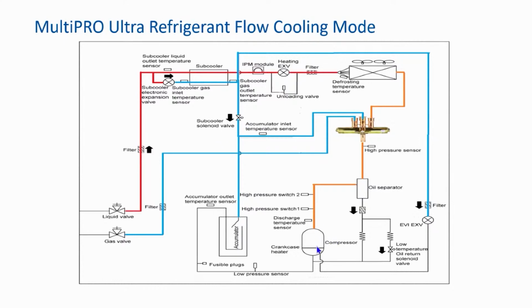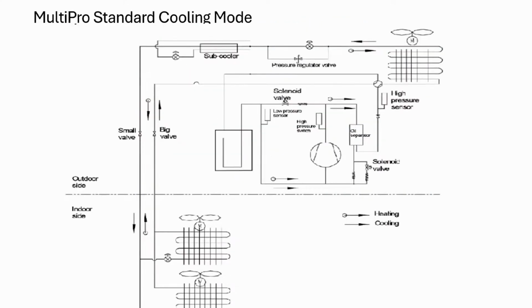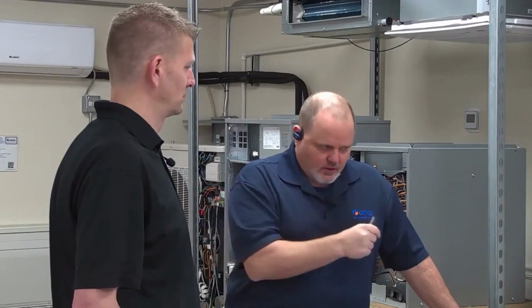In other words, the speed of the compressor, the speed of the outdoor fans, the speed of the indoor fans, what step the EEVs are at, whether you're in heating mode or cooling mode. They don't have to be wide open, right? So we'll go back to this diagram, because we need to understand this better once I get that service tool in my hand, and I'll start talking about that later on in the broadcast here. It's a building system here.